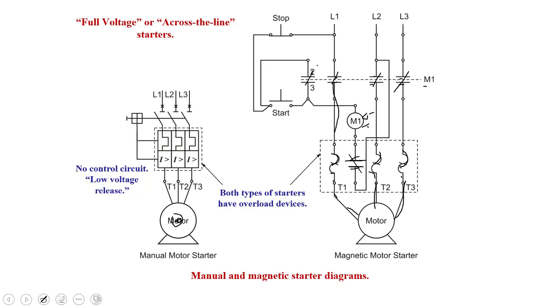So sometimes we need that type of circuit, such as a refrigerator or a furnace or freezer. If the power goes out, we want everything to start back up as soon as it comes back on. Whereas in other conditions, we don't want that, and so this one has something called low voltage protection. What that means is if power were to go out and then comes back on, the motor will not automatically restart unless somebody presses the start button. That's the only way we can get it to restart. So in certain situations, we want low voltage protection, like perhaps a table saw or maybe a conveyor, that you just don't want coming back on all by itself. You're going to want somebody to go and start it.